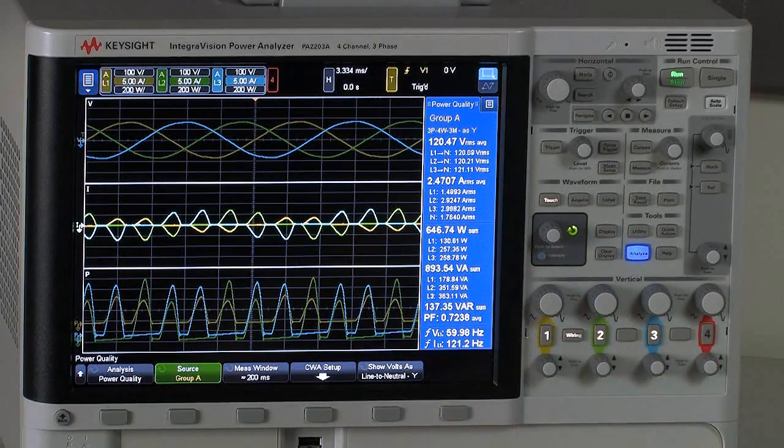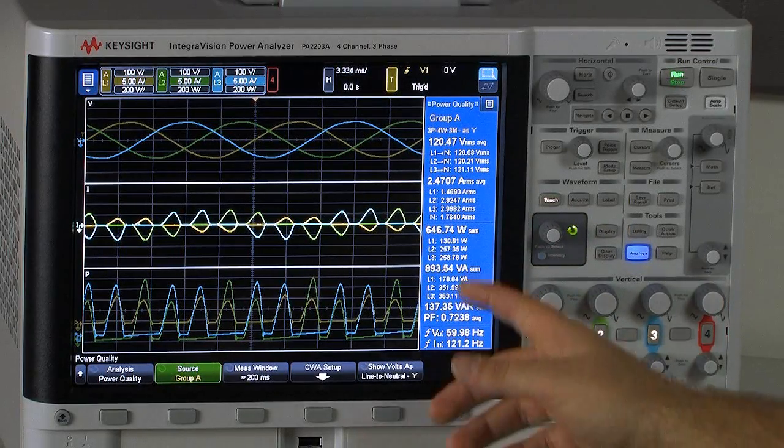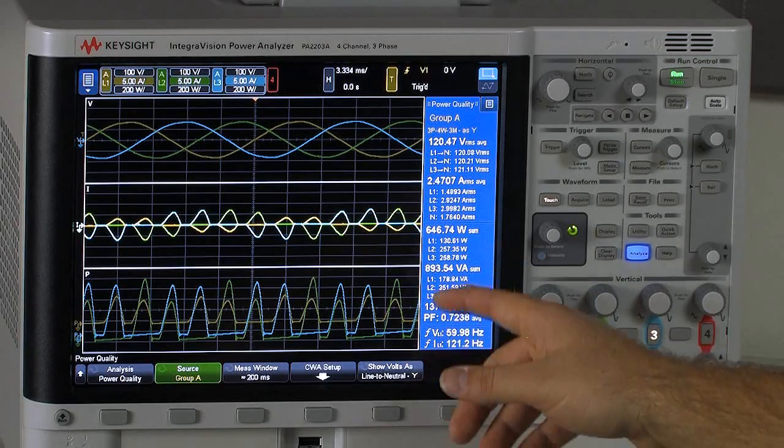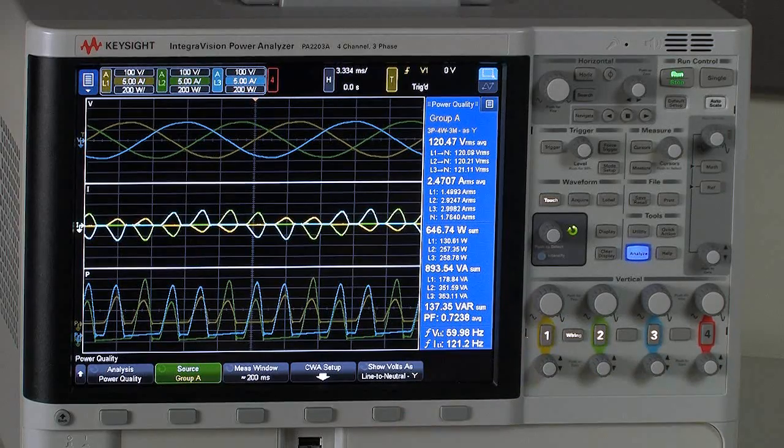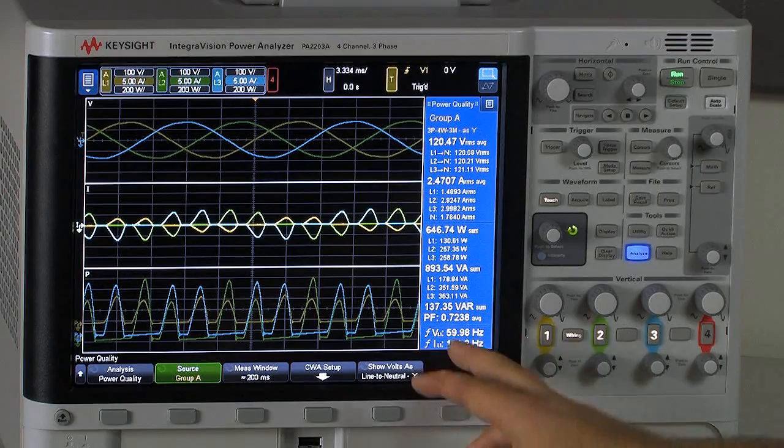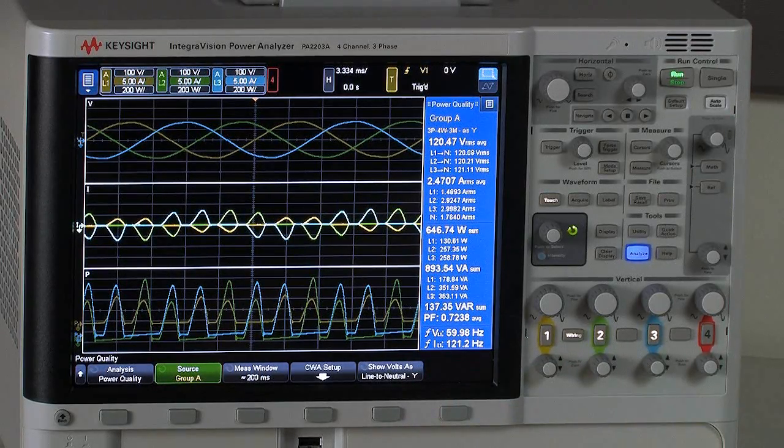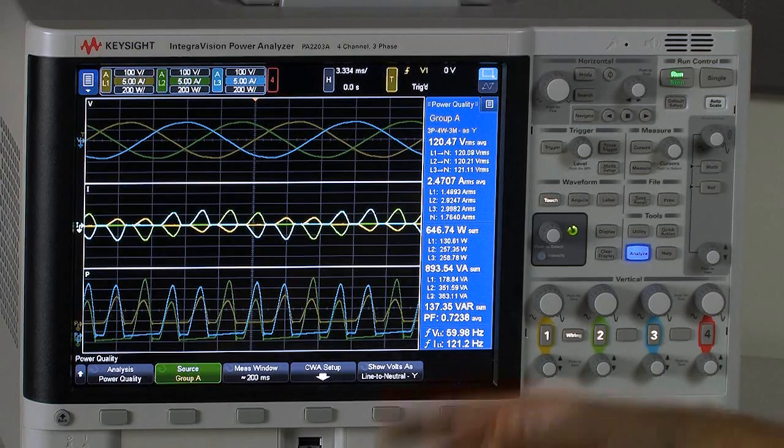And then similarly with real power and apparent power, I can see the powers of the individual phases as well as the group real power, the group apparent power, and then finally the group reactive power here at the bottom. And then of course we have power factor measurement and average power power factor measurement here at the bottom as well as voltage and current frequency measurements, which because of the nature of the rectifier I'm looking at, you can see the current frequency is actually measured to be twice that of the input voltage.